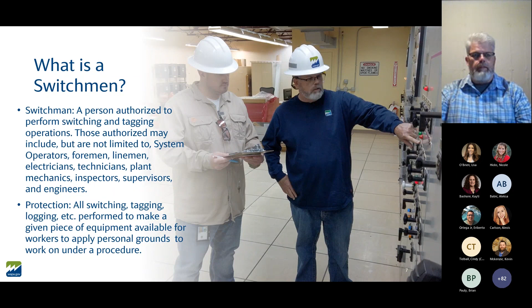When we're switching, it's all about protection, especially when establishing a clearance on a piece of equipment. All switching, tagging, logging, etc. is performed to make a given piece of equipment available for workers to apply personal grounds and work under a procedure. So it's about what type of protection or visible open point we can provide so they can work on the equipment safely after receiving their clearance.